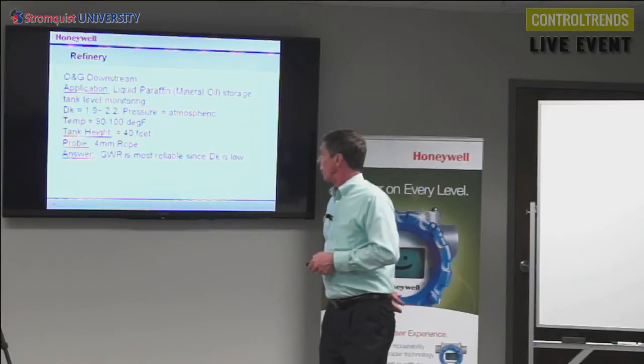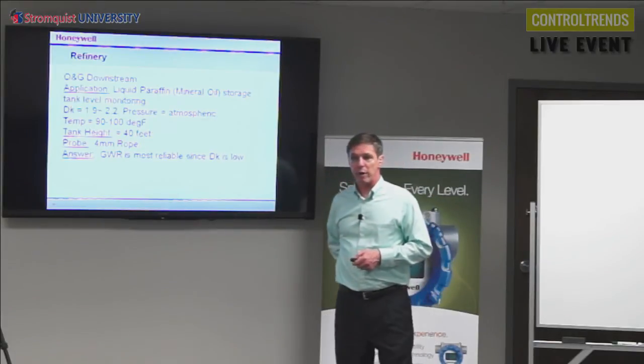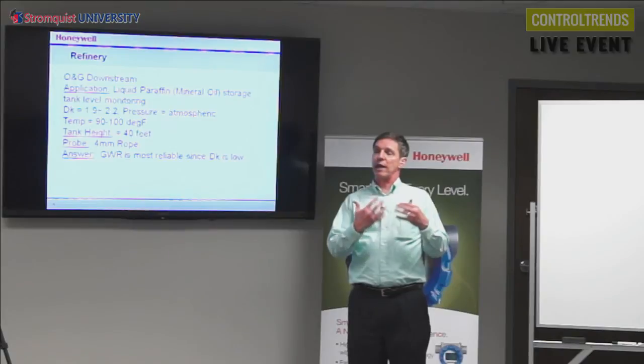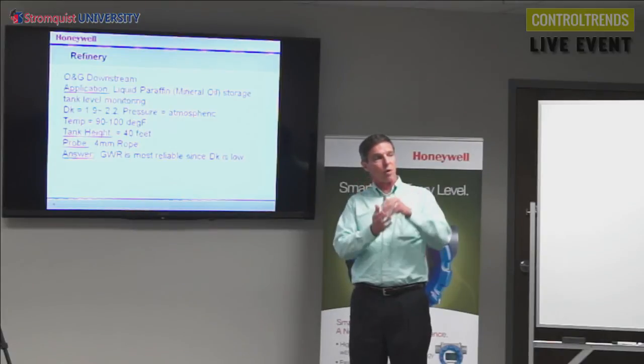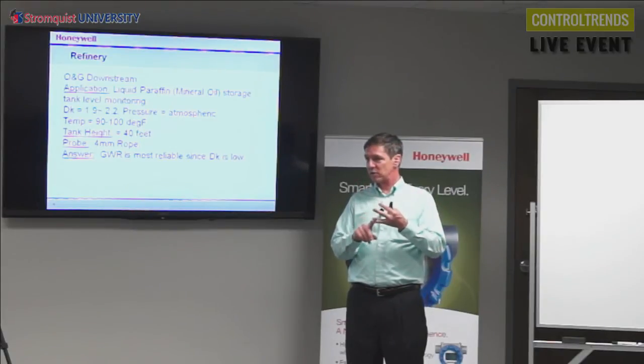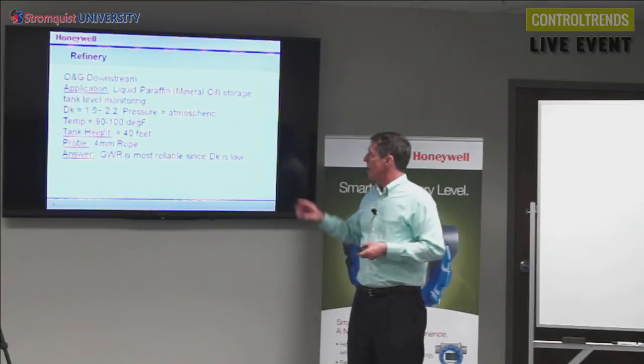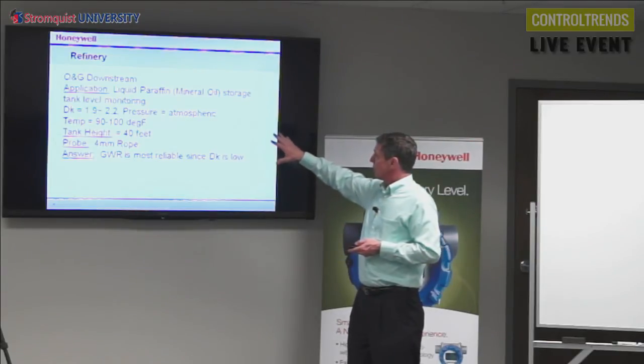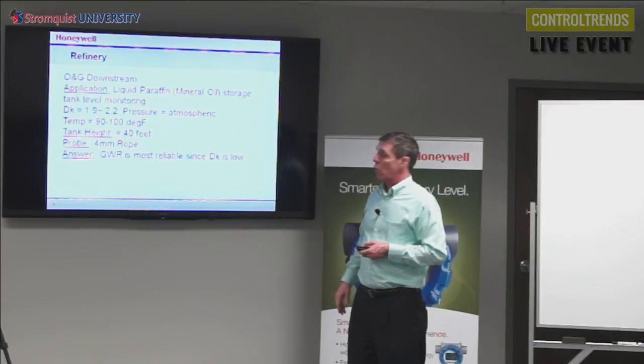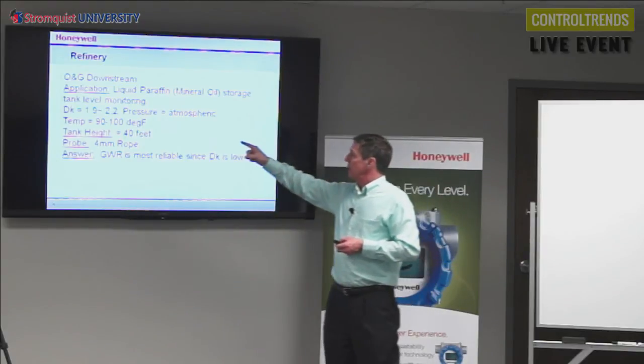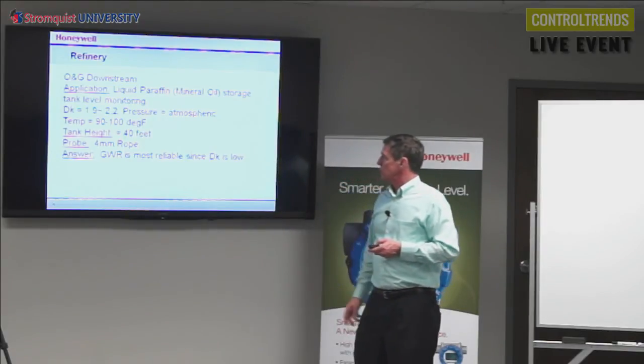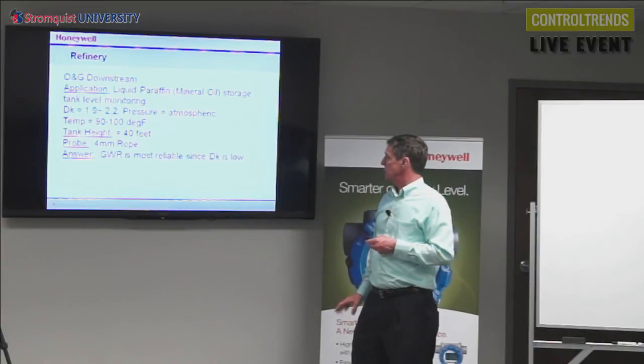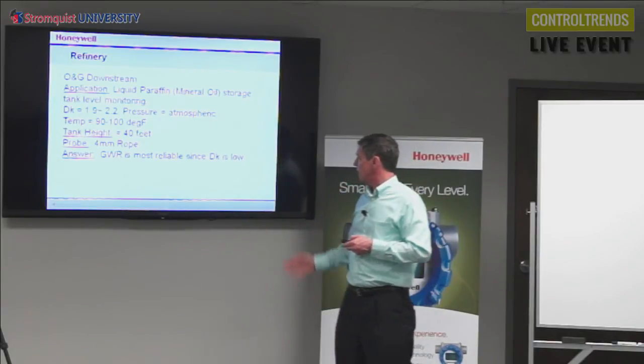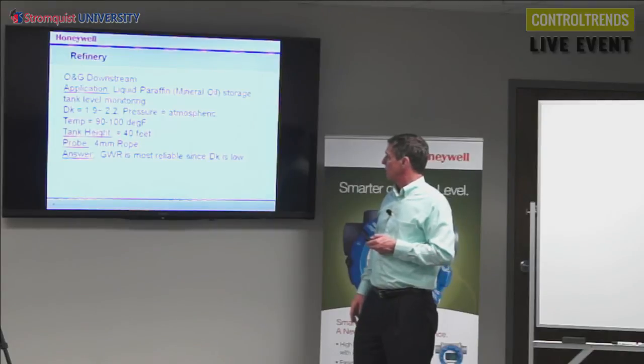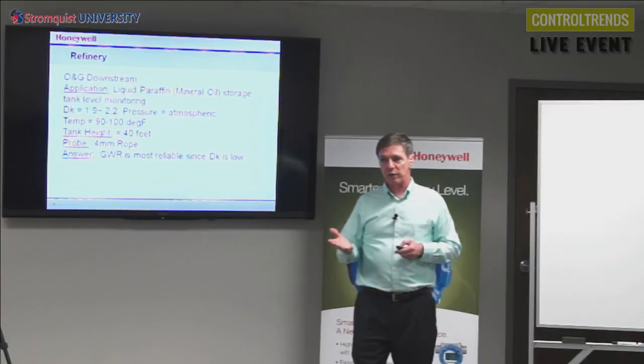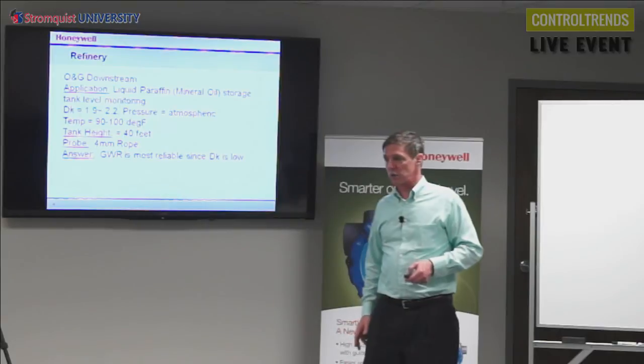This is in the refinery. There's an application on liquid paraffins. So refinery is just taking this crude oil and breaking out into all the components like gasoline and kerosene and propane and so forth. And one of them is this liquid paraffin, or sometimes called mineral oil. And its dielectric constant is around 2, which is good. The temperature, the tank height, all those things are good. And it's a good application for guided wave. Although the dielectric constant is fairly low, it's not too low to measure.